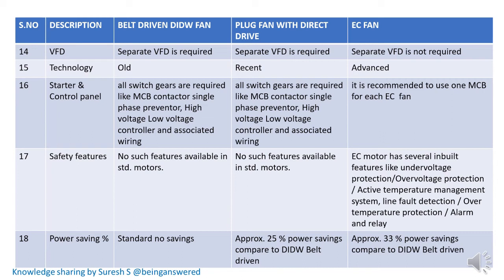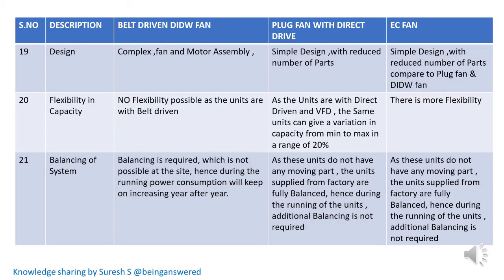For power saving, there is no such savings in the belt driven DIDW fan. With plug fan, we can save approximately 25%. Whereas EC fan, you can save approximately 33% — like one third of the power — if using EC fan compared to belt driven DIDW fan.